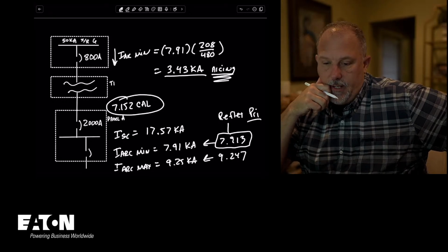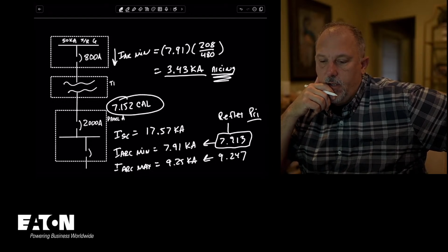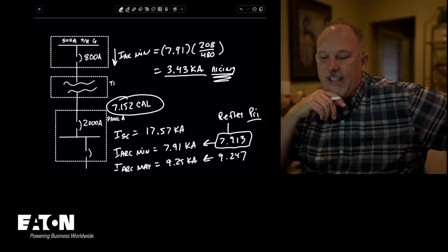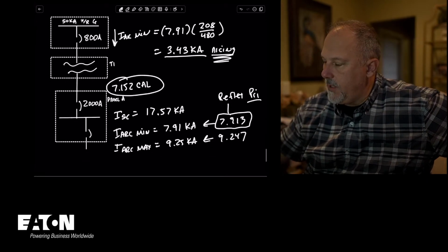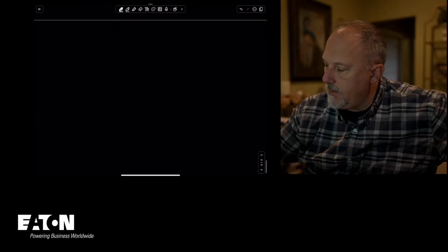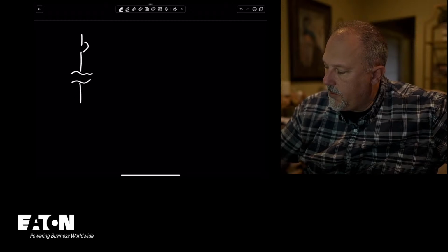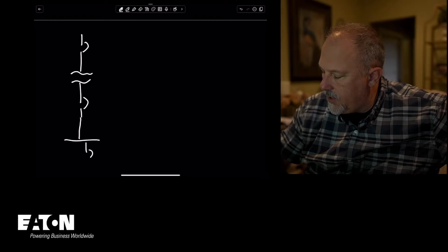Now, that's my calories at that part in the system. Alan, change that MCCB to a fuse switch for transformer protection, then use current limiting fuses. So Alan, yeah, Bussmann will thank me. So here's what I think I'm going to do, Alan. I'm going to change this up. I'm going to come down to a secondary and then a main lug only panel board.